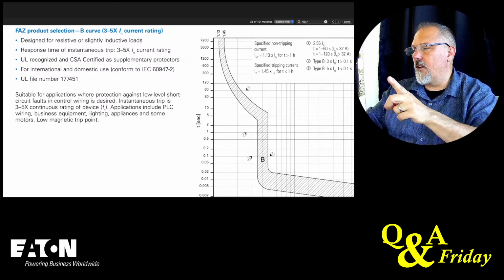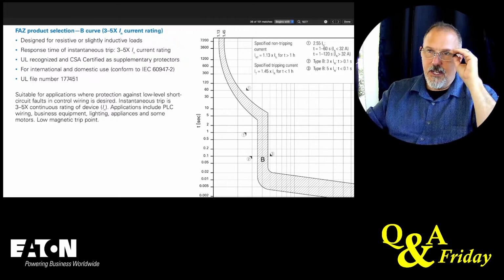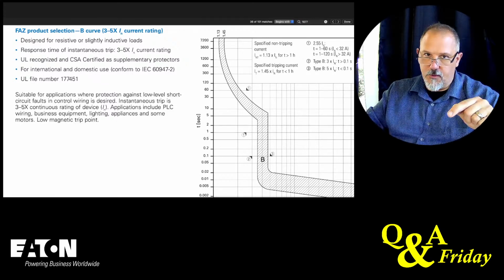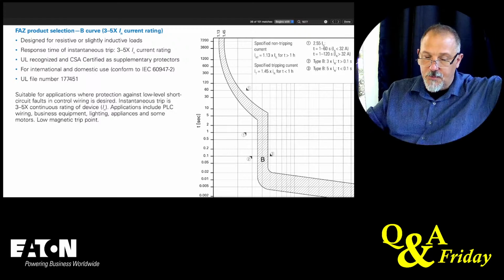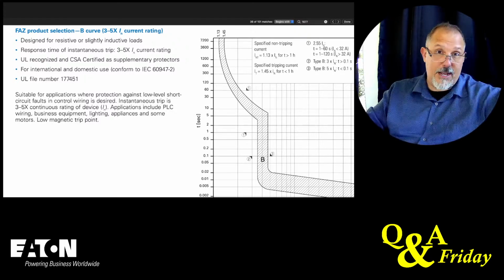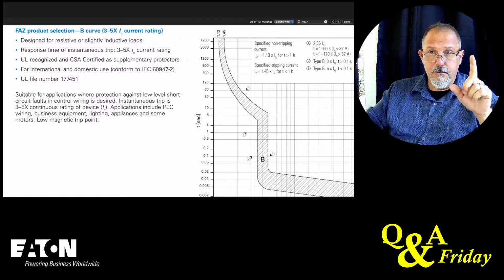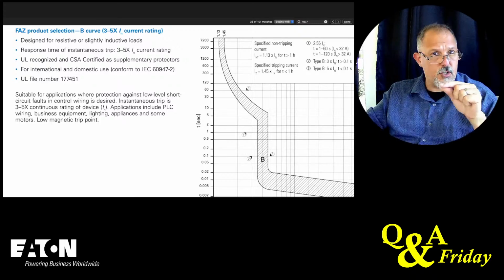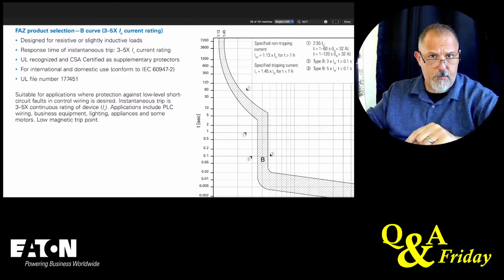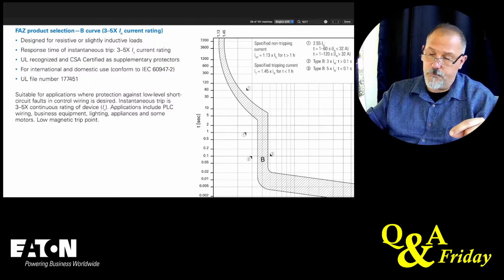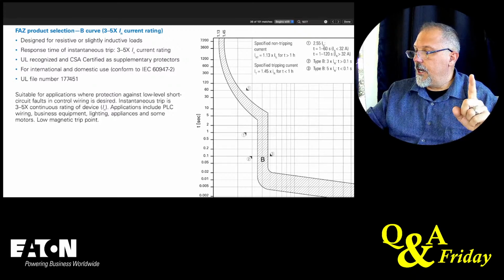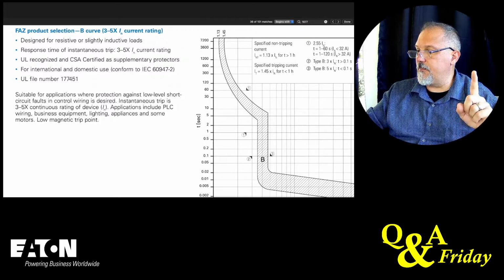Supplementary. Overcurrent protective device upstream. Yes, Felix. When you have a supplementary protector, you're going to have an upstream branch circuit overcurrent protective device. You got to, based upon the NEC. That supplementary protector, because of where it's located, is probably going to be in a piece of equipment at the end of a branch circuit. So, a huge difference on how they are tested per the UL standard.